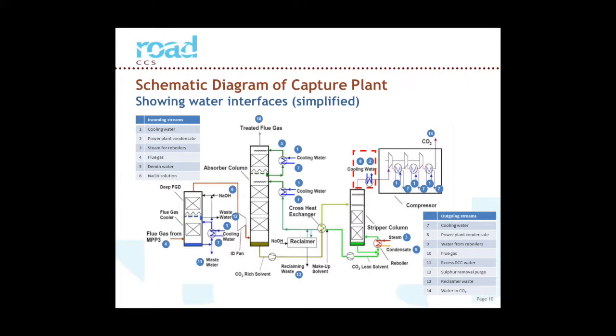The final component to understand briefly is the compressor. We did look at doing heat integration with the compressor and using power plant feed water to cool the compressor, but that has a significant disadvantage because it's warmer, and therefore you have to compress the CO2 when it's hotter. And we found with our system, because we've got very cold cooling water from the sea, the penalty in terms of compressor power that we take if we use condensate is too high. We're better off just using direct seawater cooling.